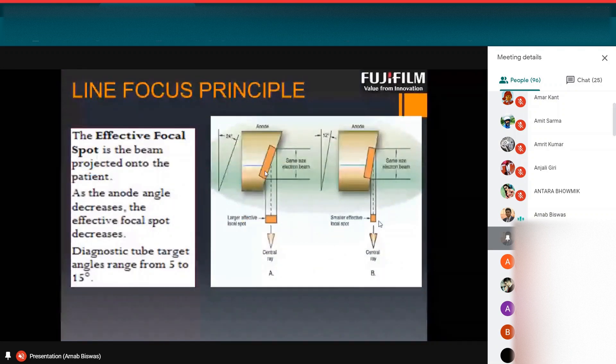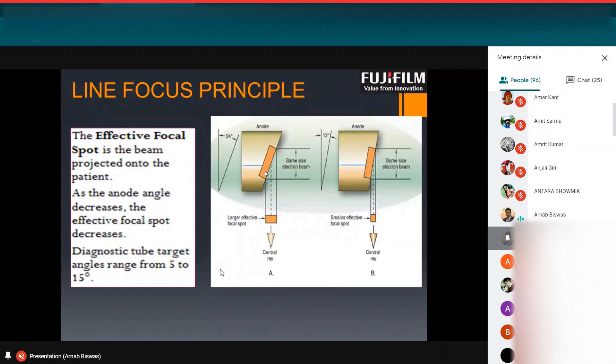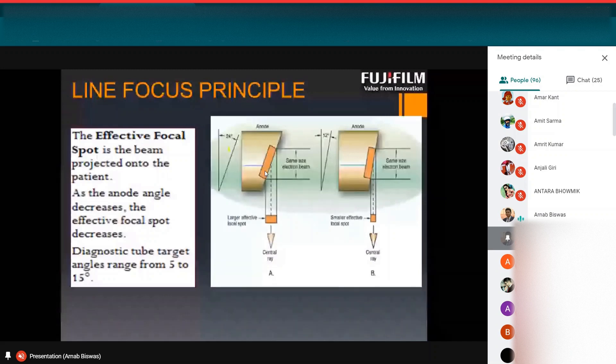I would like to discuss about the line focus principle. The effective focal spot is the beam projected onto the patient. As the anode angle decreases, the effective focal spot decreases. In this image, this is A and this is image B. In image A, you can see we use 24 degree anode angle. And in image B, you can see we use 12 degree anode angle. The electron beam size is same in both the images. But due to the difference of this anode angle, the effective focal spot is changed.